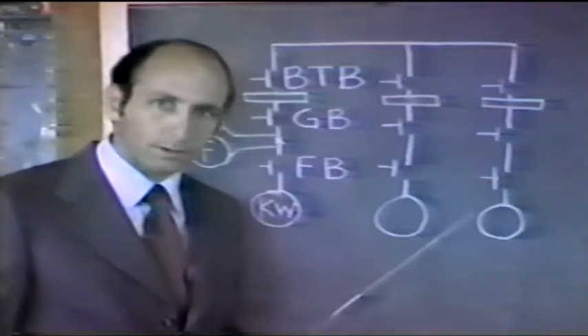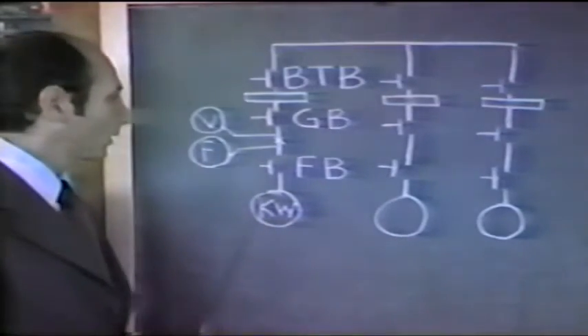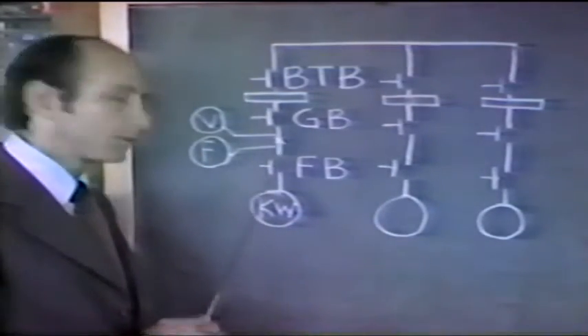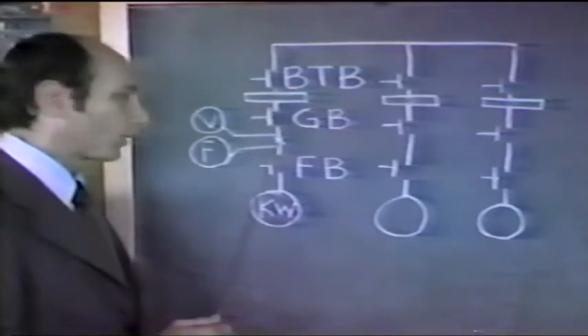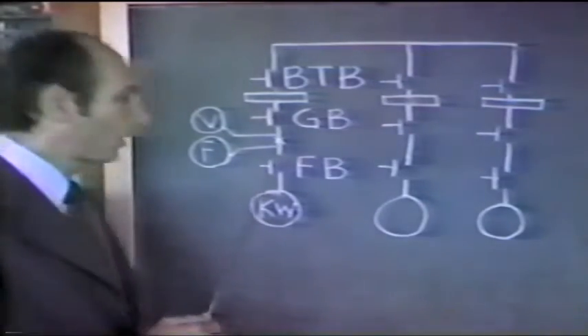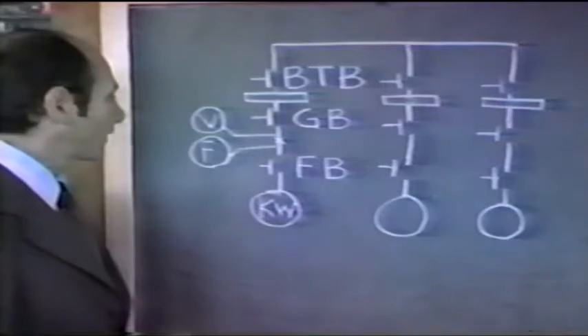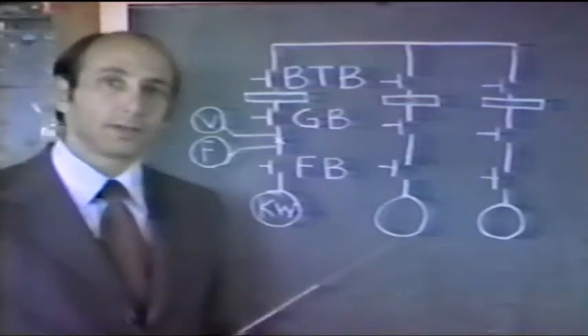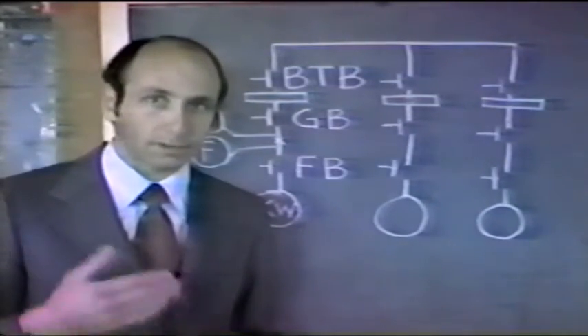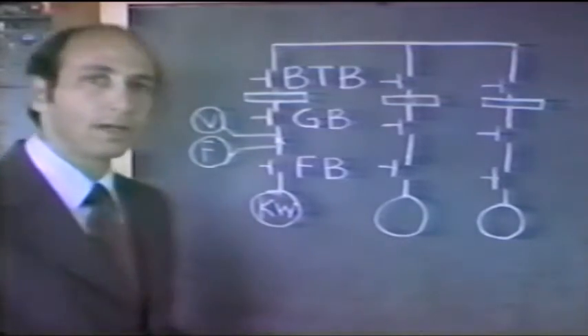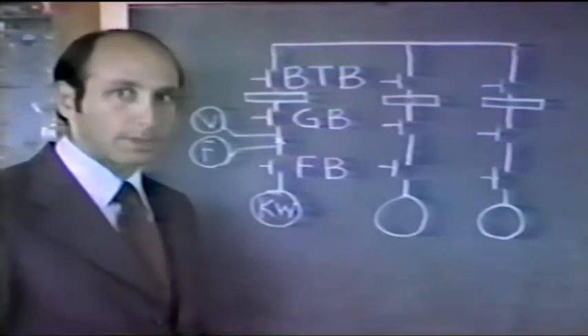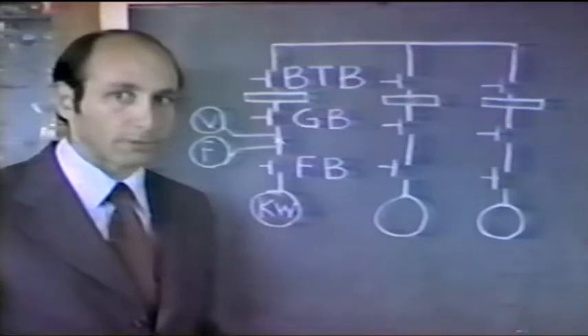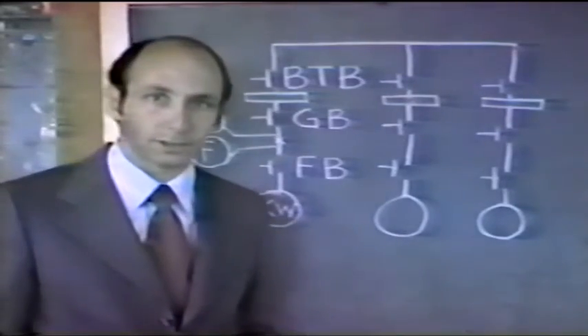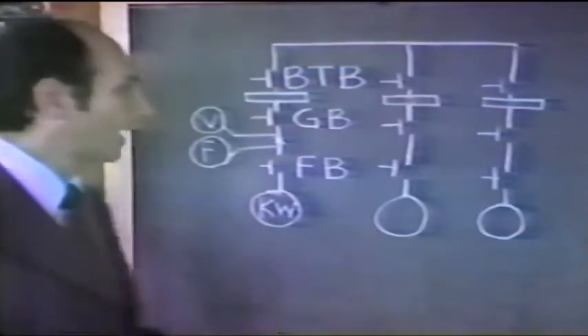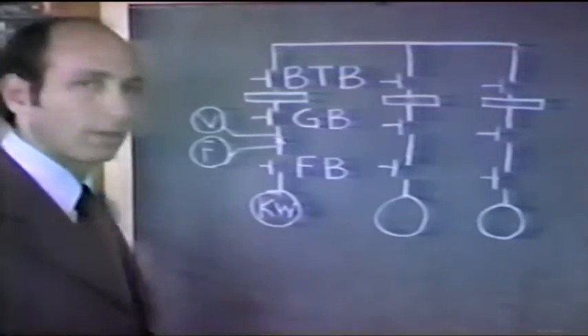And we can monitor the voltage and frequency of each generator just downstream of the field breaker. So once we turn the generator on, we can check the voltage and the frequency. And of course, that would be necessary to make sure that our generator is within limits prior to placing the load bus on the generator, because then if we did not have proper voltage and frequency, we could do some damage to some electrical equipment. Okay, is that the entire AC system? Well, of course not.